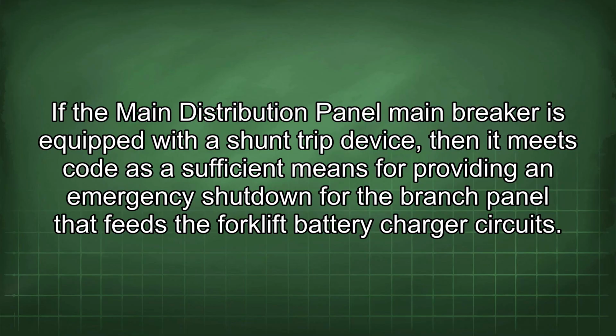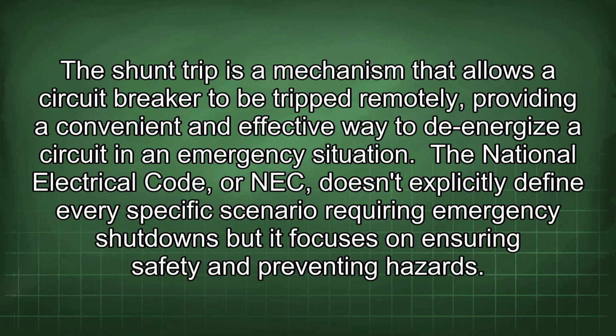The main distribution panel main breaker is equipped with a shunt trip device, then it meets code as a sufficient means for providing an emergency shutdown for the branch panel that feeds the forklift battery charger circuits. The shunt trip is a mechanism that allows the circuit breaker to be tripped remotely, providing a convenient and effective way to de-energize a circuit in an emergency situation.